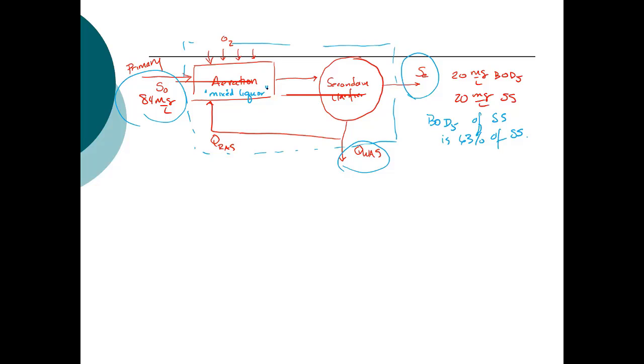So that BOD5 of suspended solids being 63% of the suspended solids, is that on top of the 20 milligrams per liter BOD5 you already have? No. So this is the total BOD. What we need to do to design is we're designing the entire system based on soluble BOD. So this 20 is the total.